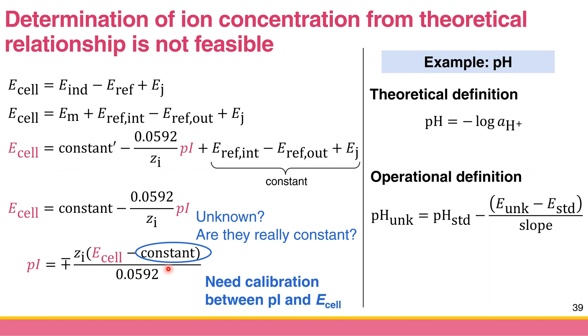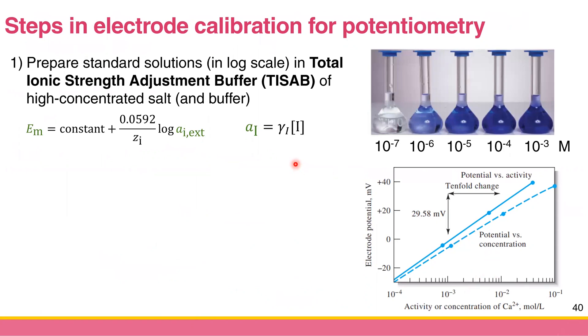Let's consider this figure. We prepare a series of ion concentrations — maybe 10⁻⁷, 10⁻⁶, 10⁻⁵, 10⁻⁴, and 10⁻³ — because we plot against the p_ion, which is the negative log of concentration. For linearity, the plot against the exponent should be linear. But the problem is we always assume activity equals concentration, and the membrane potential operates on activity.